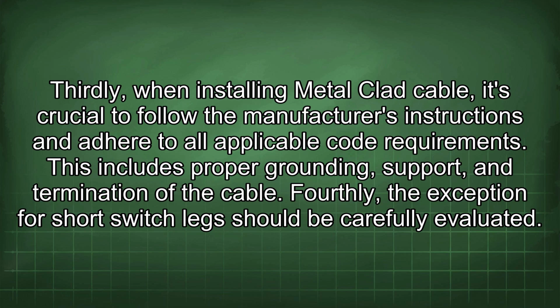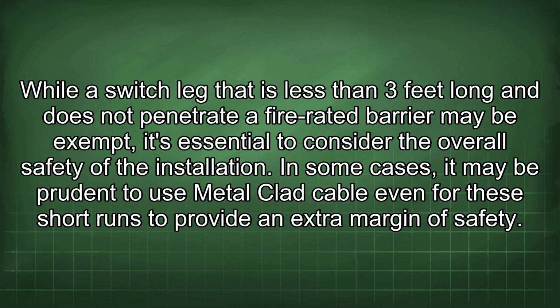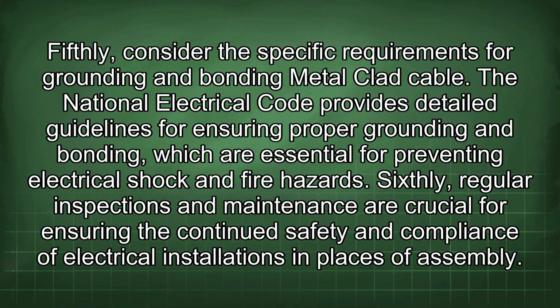Fourthly, the exception for short switch legs should be carefully evaluated. While a switch leg that is less than 3 feet long and does not penetrate a fire-rated barrier may be exempt, it's essential to consider the overall safety of the installation. In some cases, it may be prudent to use metal-clad cable even for these short runs to provide an extra margin of safety. Fifthly, consider the specific requirements for grounding and bonding metal-clad cable.